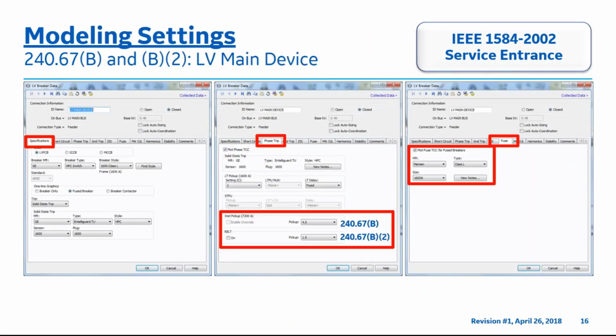In the Specifications tab on the left, the electronic device shown here would be adjusted per the appropriate trip settings to achieve coordination and/or selective coordination per the NEC requirements in a low voltage power distribution system. In the Phase Trip tab in the center, the instantaneous pickup is highlighted in the red box. A pull-down menu is available from some software programs to help adjust the instantaneous pickup settings, which allow for proper coordination and/or selective coordination, along with meeting the specification clearing time requirement of the 240.67B paragraph. The instantaneous pull-down menu allows the time current curve to be moved from the left with a value of 2.0, ultimately to the right at a value of 10.0.